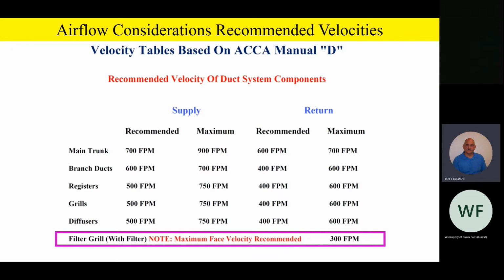So all of these things become, again, really important when you're putting in a system in general, but also these modulating systems. We want to make sure we give them the right airflow, and we want to make sure that the velocity across those key components like main trunks and branch runs and all that, and registers, are within Manual D recommended velocities as we build that duct system out.